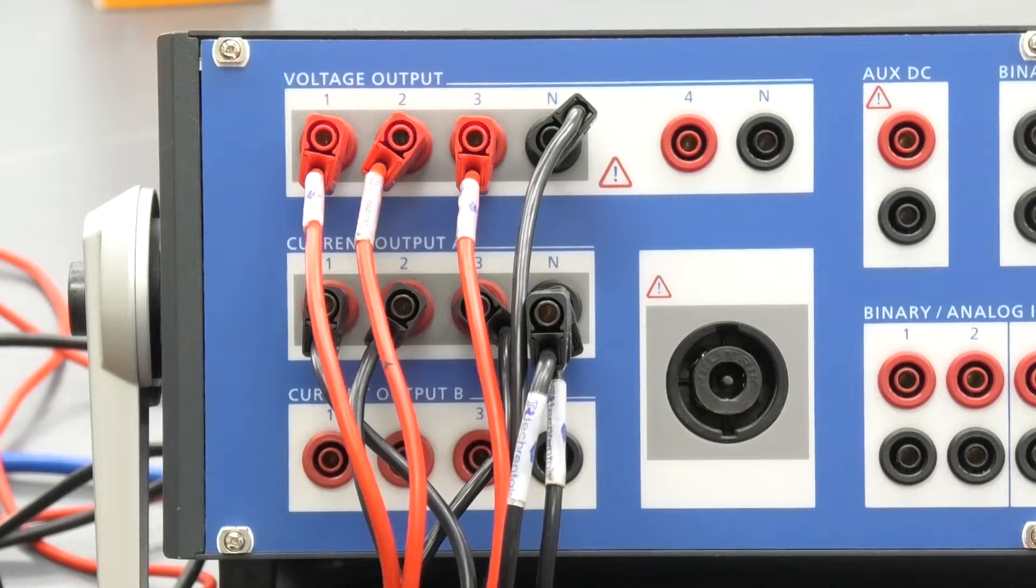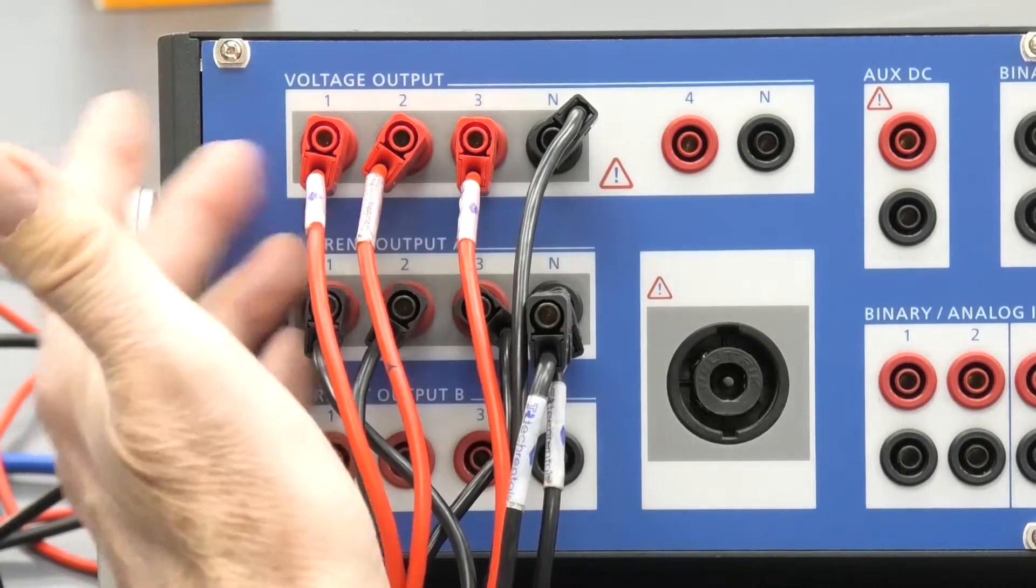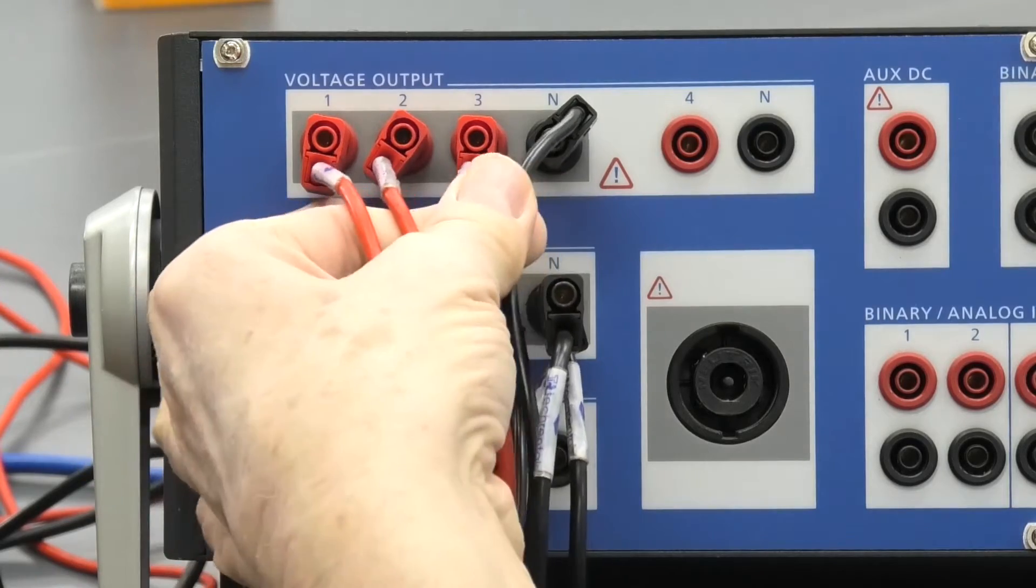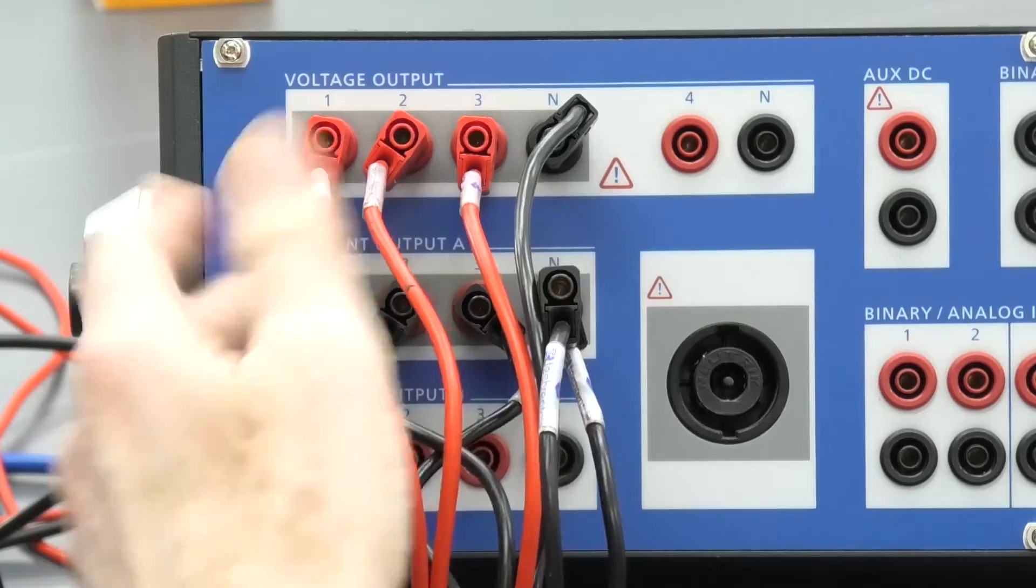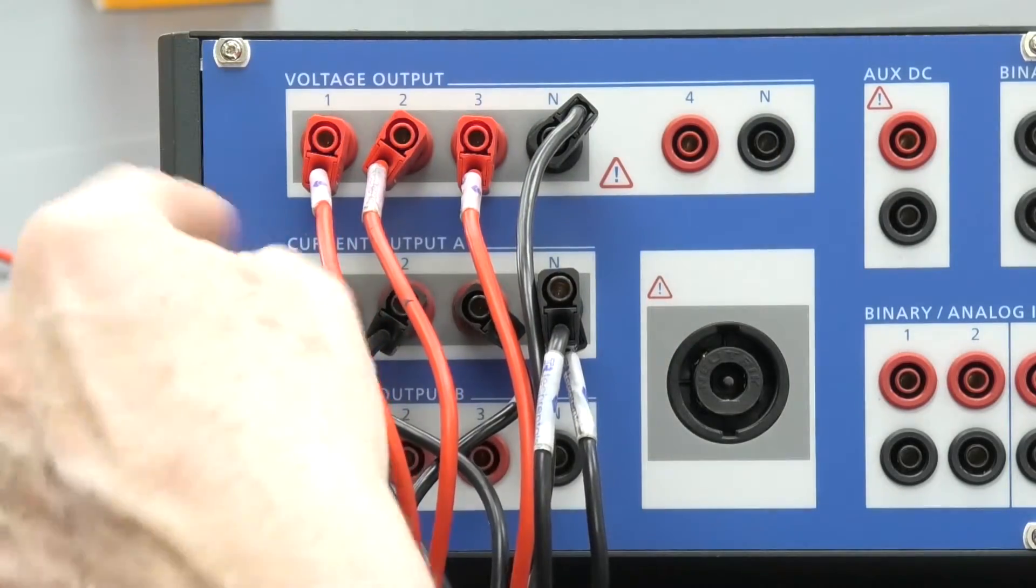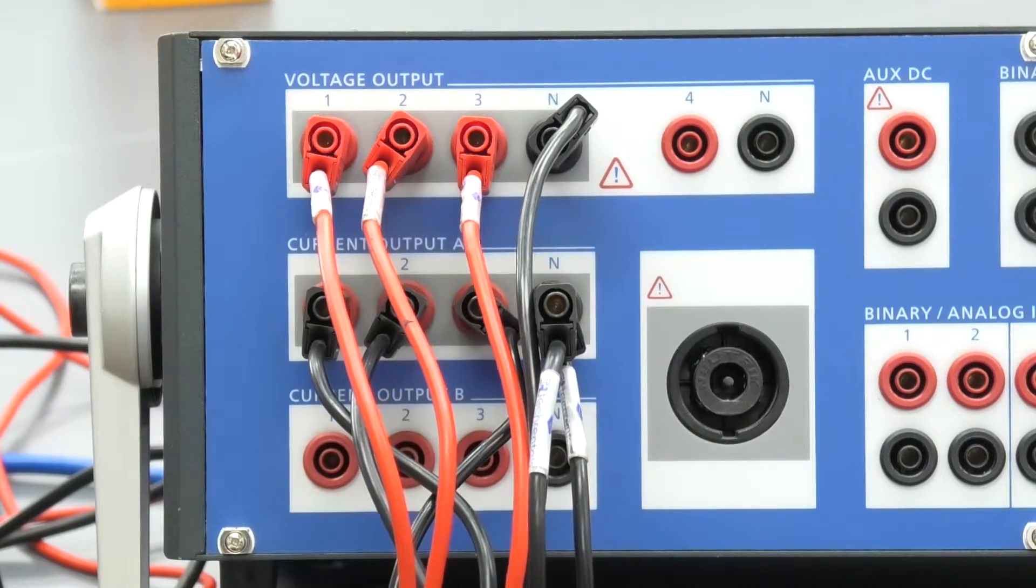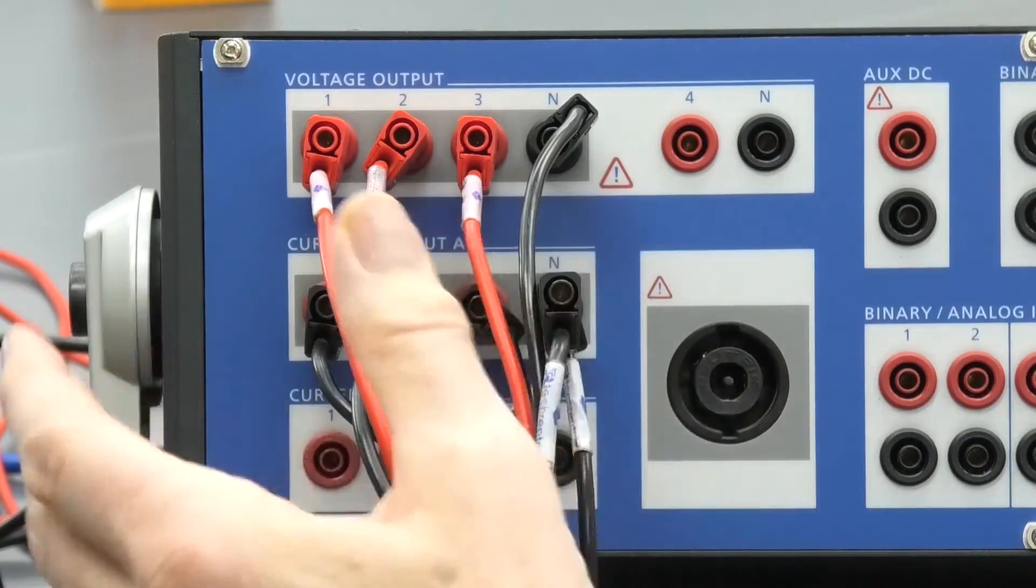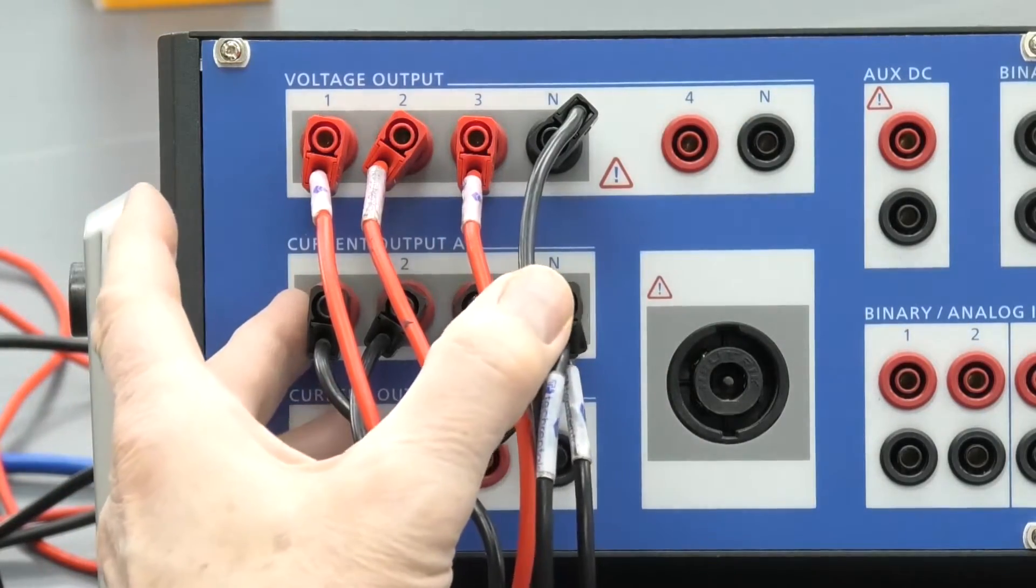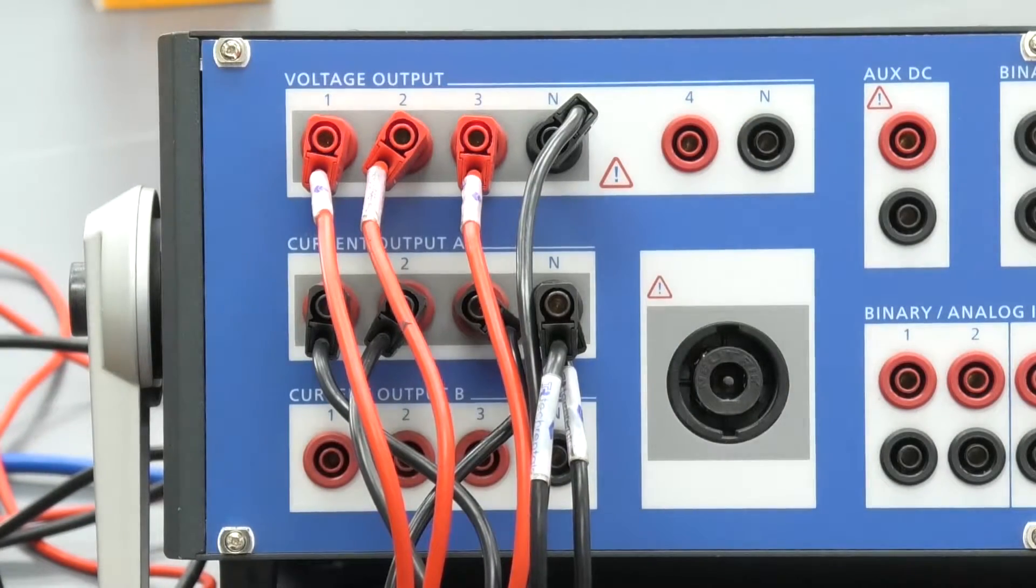Just to show this thing functioning, what I've done is I've just wired up a power analyzer, the three voltage inputs and neutral input to these voltage outputs. I've wired up the current outputs. I've run these wires through the current clamp and I've twisted them five times around, so they'll give a reading five times higher than the settings we've put over here. So I've got three current clamps and the three voltage measurements set up here.